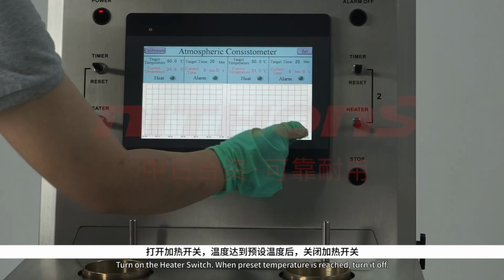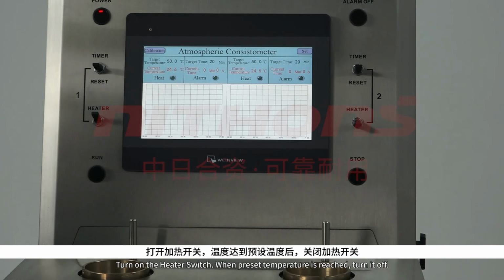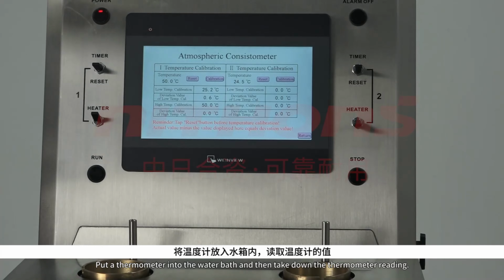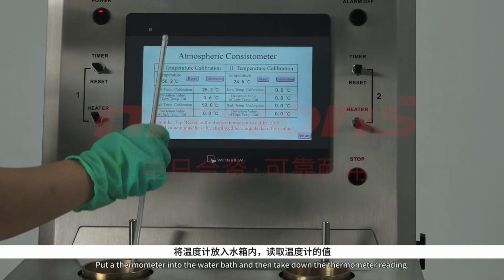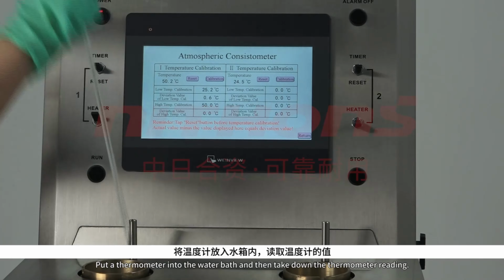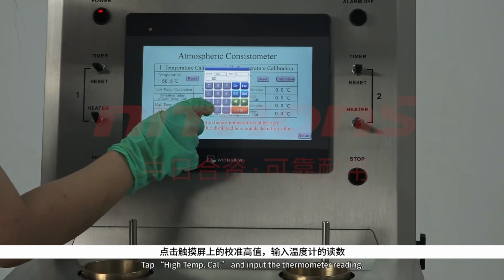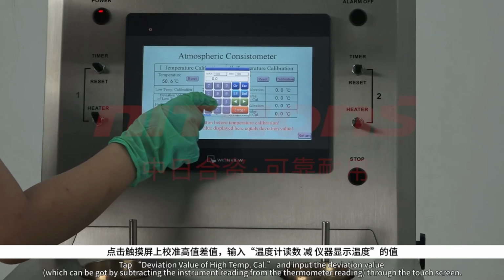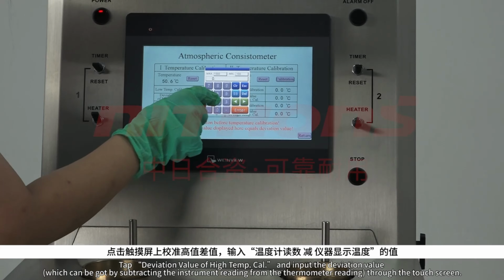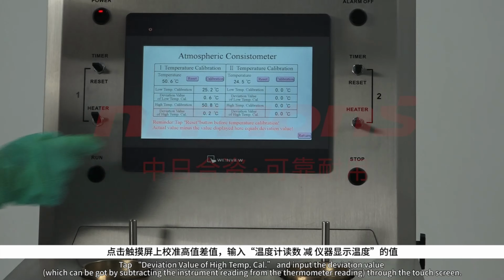Turn on the heater switch when preset temperature is reached. Turn it off. Put a thermometer into the water bath and then take down the thermometer reading. Tap high temp.cal and input the thermometer reading. Tap deviation value of high temp.cal and input the deviation value through the touch screen.